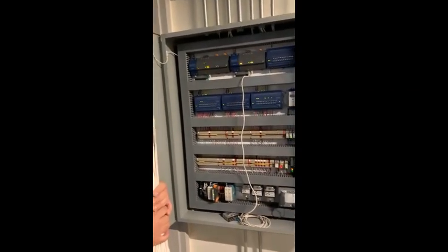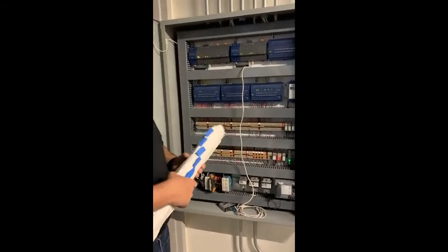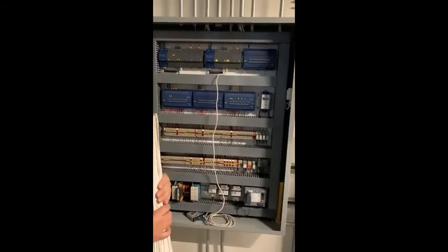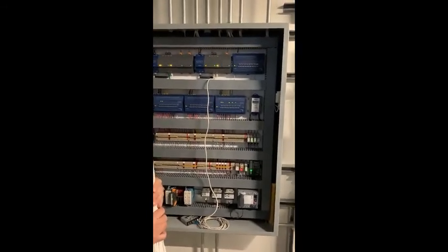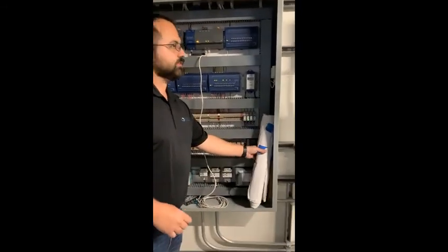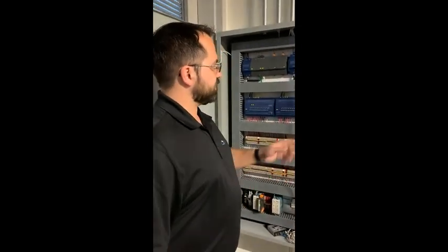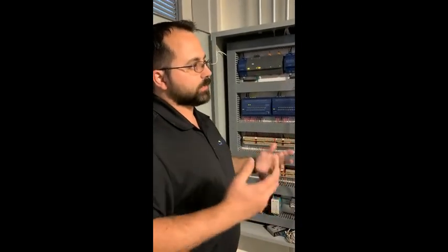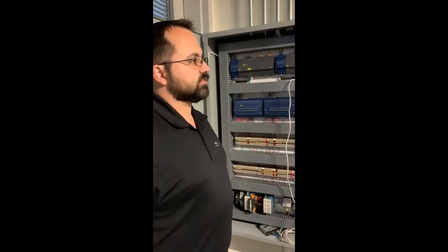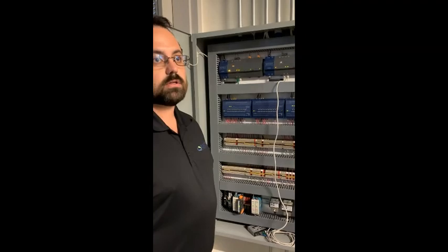Yeah. But we're waiting to hear from the manufacturer for a solution to the issue with doing some global commands and stuff. Like I said, it's the 8th floor one right now where the Jace has been removed. We have an industrial PC in there running the station, and instead of these LON modules, we have a LON IP router doing the communication. But yeah, we're waiting to get a final word on the solution, how we're going to move forward, and we'll determine that for you guys.